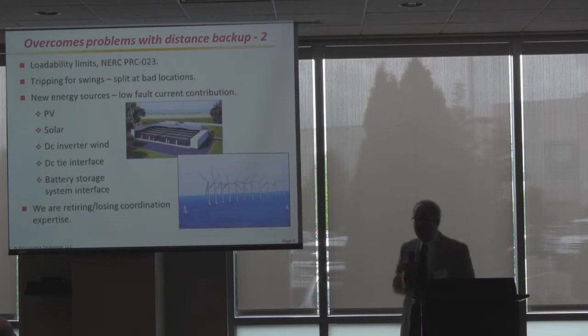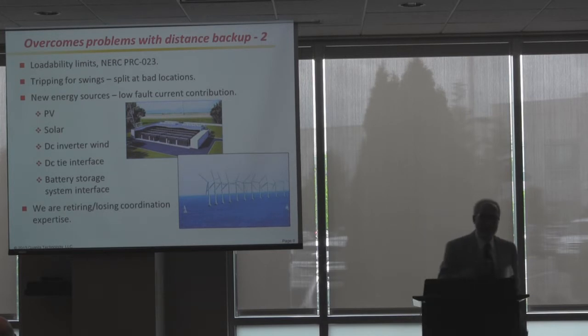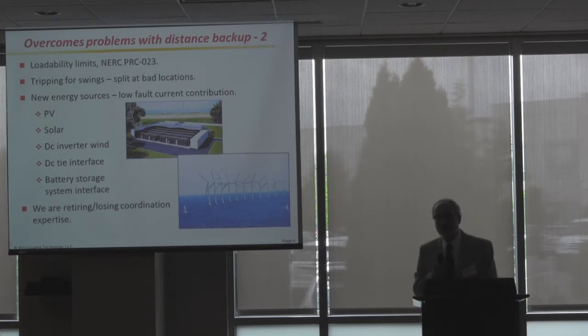And there are more problems. In recent years, we've had loadability limits that came to us after the 2003 blackout. We have new energy sources that I've pictured here, which have low fault current contributions, in some cases making it harder for us to figure out where the fault is or to set these distance relays properly. And maybe something that's observable and not technical is that all the folks who knew how to deal with these problems are retiring. We're losing this ability.